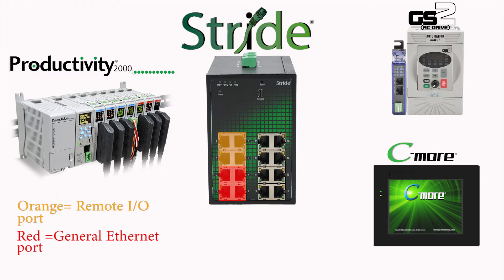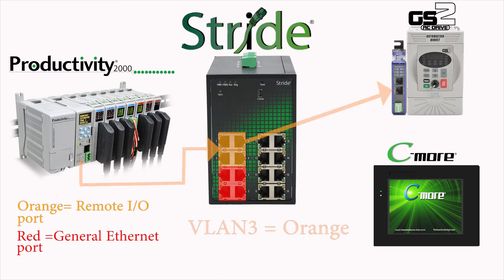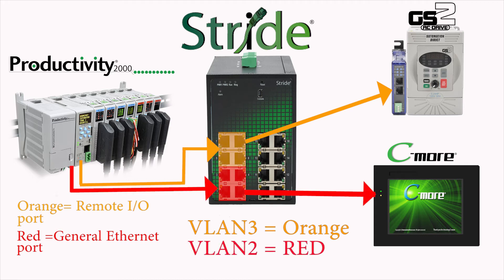With VLAN, segregating this network is simple. The Remote I/O port of the Productivity 2000 and the Remote I/O Drive are plugged into ports set up for VLAN 3 on ports 5 through 8. The HMI and the other Ethernet port of the Productivity 2000 are plugged into ports set up for VLAN 2 on ports 1 through 4.